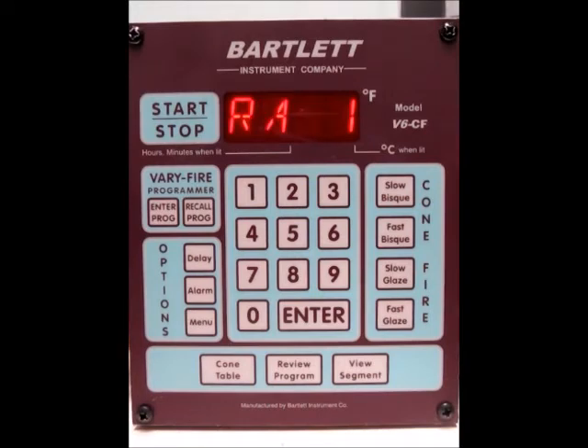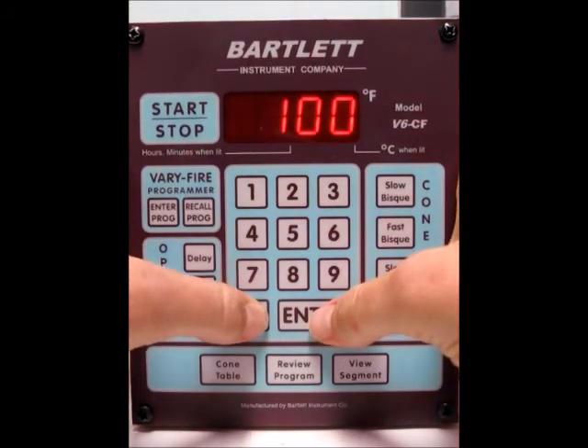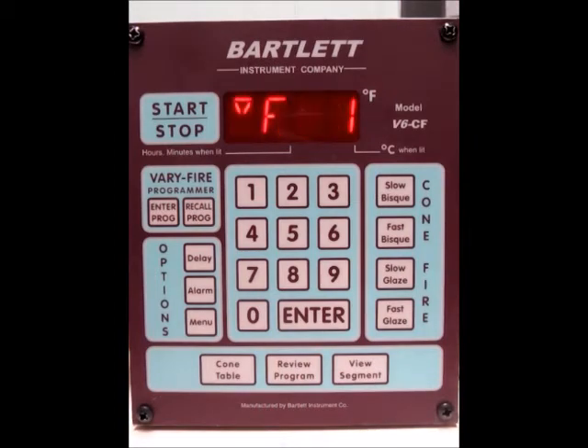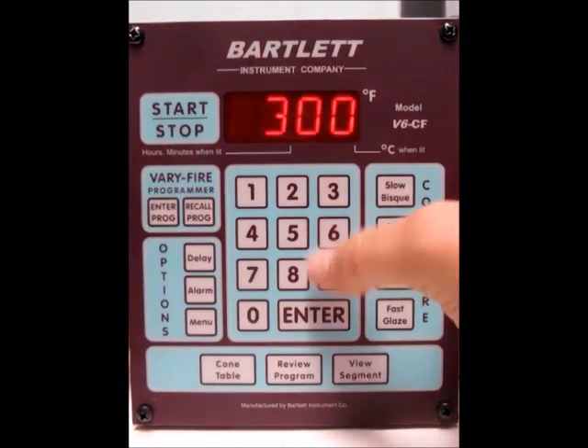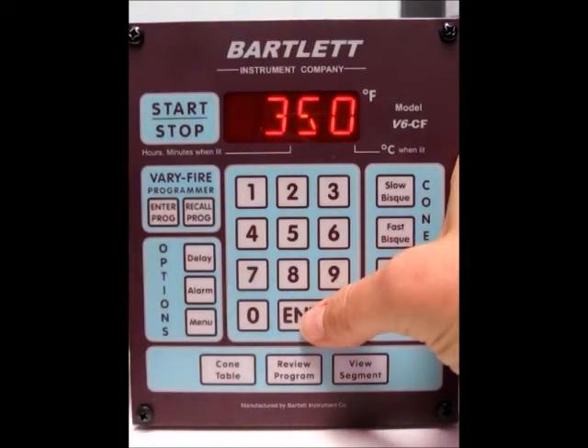Now it's asking you for the ramp rate for segment number 1. Right now it's at all 9's, which is as fast as possible. I'm going to change it to 100 degrees per hour, so type in 100 and press enter. Then it's asking you for the temperature for segment number 1, so we'll type in 350 and press enter.